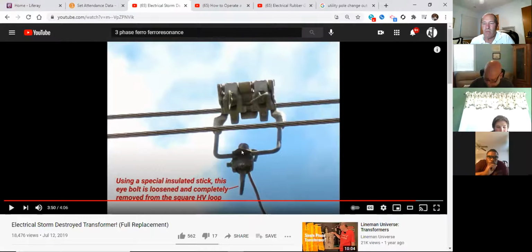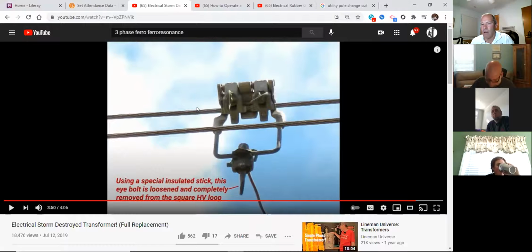If I take this and put it directly on the wire like we're doing, and it fails, what's going to happen? It's gonna fail everything. You're right, you're going to burn the wire in two, and the primary is going to go down to the ground, and everybody on this conductor is going to lose power. So I wouldn't call it isolation. It's a connection point here, so if you have a failure, you're only going to lose what's at the connection. If you put it directly on the primary conductor, it's coming to the ground.